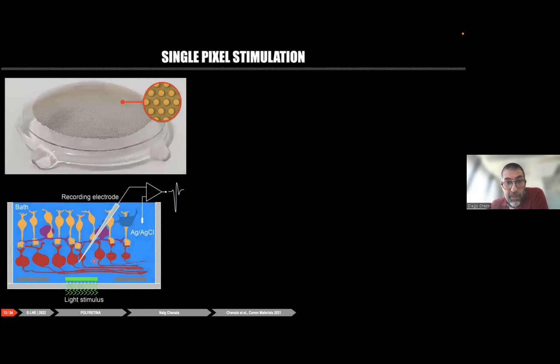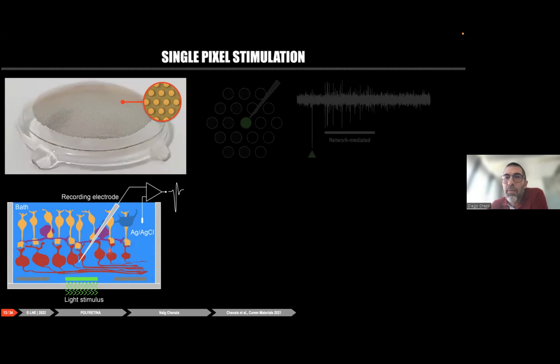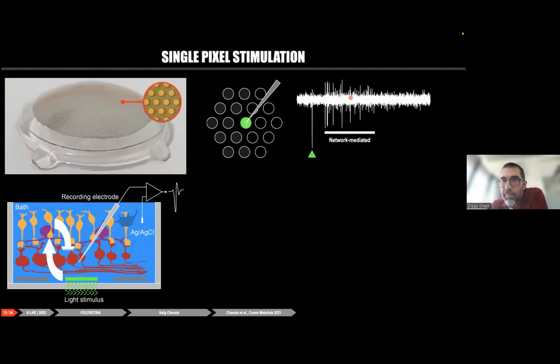So we took the explanted retinas and put them on top of the device. We use microelectrodes to record from retinal ganglion cells on top of the illuminated pixel. We have a pattern stimulator to illuminate only 1 pixel of the device, and we record the retinal response. You see here what is called the network-mediated response. It's very delayed from the onset of the pulse. The light is a green pulse of 10 milliseconds. Here you see clearly the stimulation artifact.